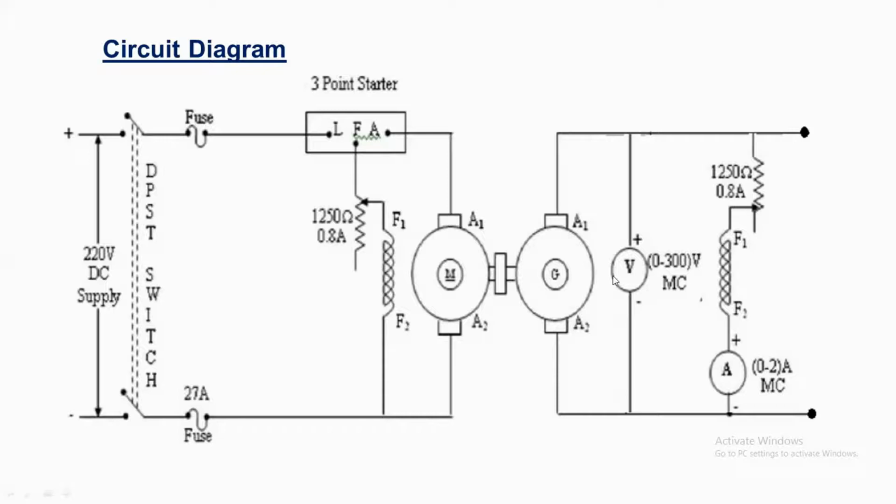After that, reduce the resistance from its maximum to minimum in steps. If the resistance is reduced, some field current will enter the field winding. It is because at starting time, full resistance is added and no field current enters. Only the generator has some residual magnetism. The residual magnetism induces a voltage at the armature terminals, and only that voltage is shown in the voltmeter.